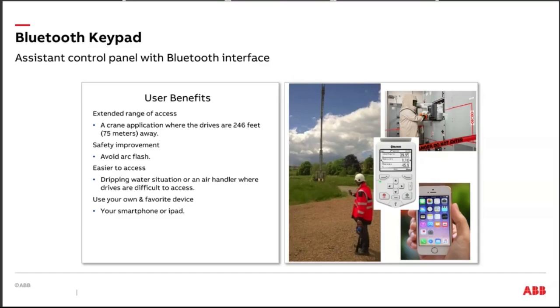Now, I don't have to do that. I don't have to open up that door and put clamp-ons on the motor leads. I don't have to stand there in front of the open door, reaching around the backside, increasing the speed of the drive with a speed pot or something like that. I can leave my doors closed. I remove myself, my person, from that arc zone because my door is closed and it's bolted down.